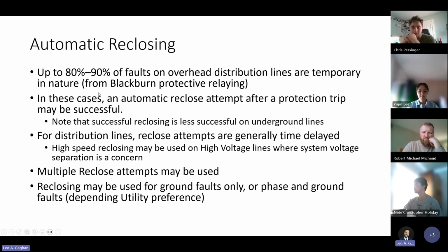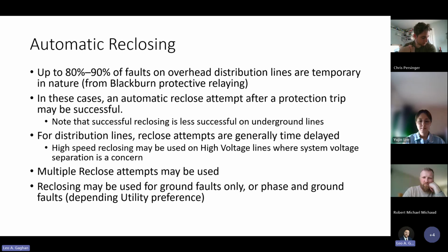So, automatic reclosing. I know we've talked about it a lot. Maybe we've gotten a little bit ahead talking about it, but it plays into a lot of the other things that we've been working on. So I think we said up to 80 to 90% of faults on overhead distribution lines are temporary in nature. Think of that squirrel getting fried and then falling off. When we do have one of those temporary faults, it's good to try to do an automatic reclose, because we might be successful. I did want to note, successful reclosing is much less common on underground lines, so you probably wouldn't have reclosing on underground lines.